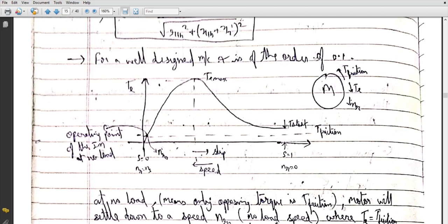If there were no frictional torque, the rotor would reach synchronous speed where electromagnetic torque is zero and acceleration is zero. But in a practical machine there is always friction, so nr can never equal ns. The point where electromagnetic torque equals frictional torque is the operating point of the induction motor at no load.